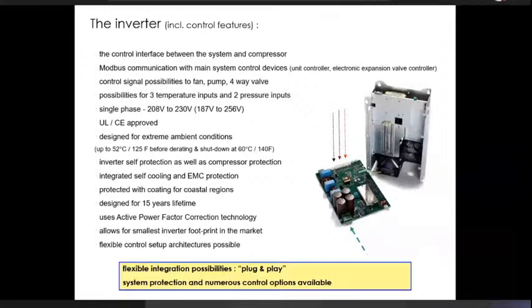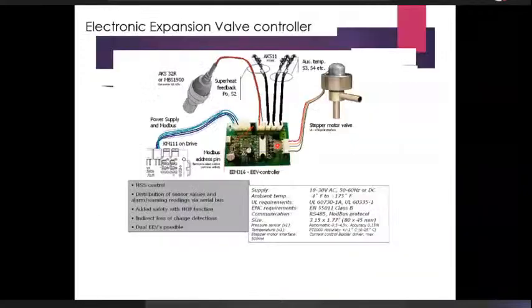Then there is a need to know the superheat. An expansion valve is expected to maintain a constant superheat at compressor inlet. So we need temperature sensing, pressure sensing, and some other functions like indirect loss of charge detection, which is, if refrigerant leaks, can we find that out? And can we define what maximum pressure we will allow this unit to operate at? Because the evaporator is at part load, the pressures can go high, so we need to have that built in. We need to comply to standards, we need to comply to EMC requirements, we need good communication, and we also need to fit this in a particular size. So all of this is important.